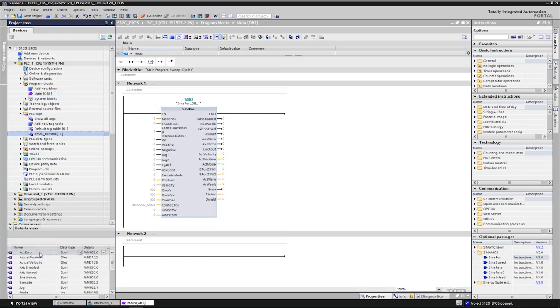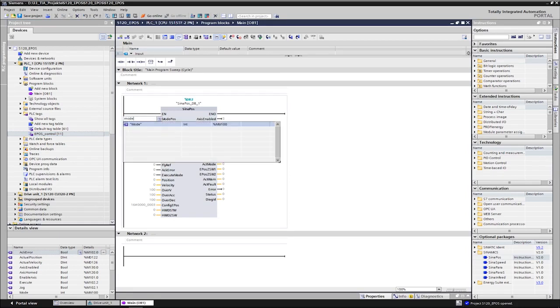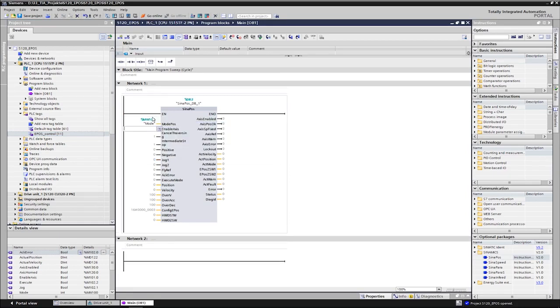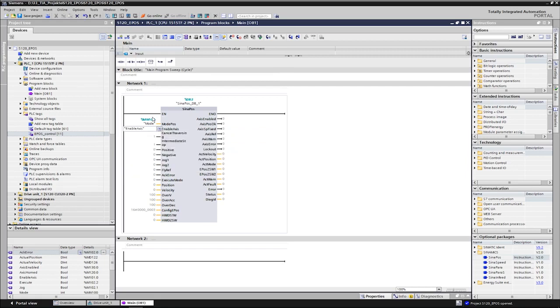For our example, we just connect some of the most important inputs and outputs. We start with the mode input to select the different operating modes of the basic positioner. The enable axis input is used to switch the drive on and off. Cancel traversing means discarding and cancelling a motion task and must have a one signal for positioning to be performed as it is switched to low active.